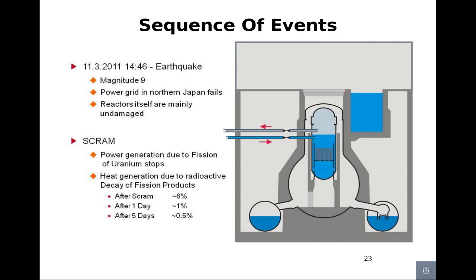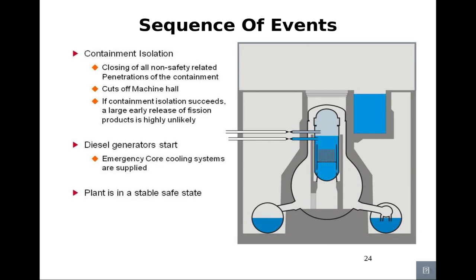You can see the earthquake happened, the plants initially scrammed, but there's still decay heat products. Containment isolates, closing off all non-safety related penetrations of containment. This cuts off the machine hall, and if containment isolation succeeds, a large early release of fission products is highly unlikely. The diesel generators start, and emergency core cooling systems are supplied. The plant is in a stable state.